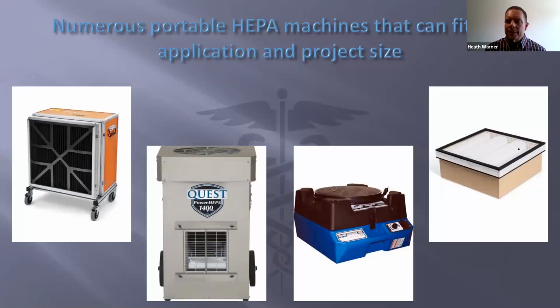Finally, like I mentioned earlier, just normal HEPA filter machines. There are so many different sizes available for all size jobs, if you can find them and they don't sell out nationally. The other tip that I usually will throw in here, most people don't realize, almost all HEPA filters have the ability to not only run HEPA filtration, you can actually run a carbon pre-filter in them. They're not cheap either, neither are HEPA filters, but that carbon filter will take out 99.9% of the VOCs that are cycling through, so there's no fumes going through. Really popular in museums and hospital applications.